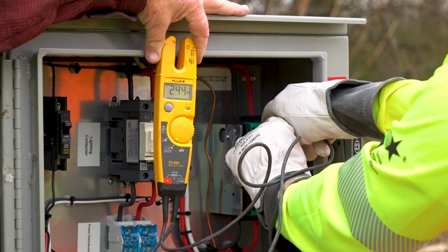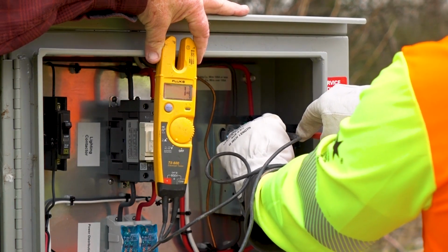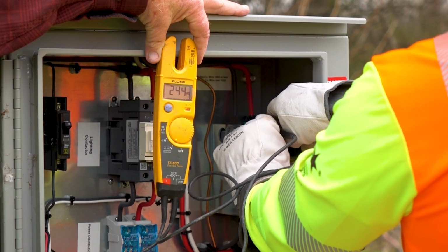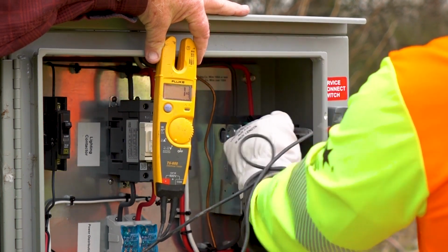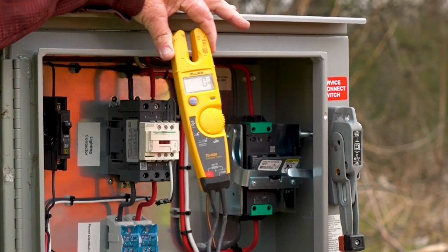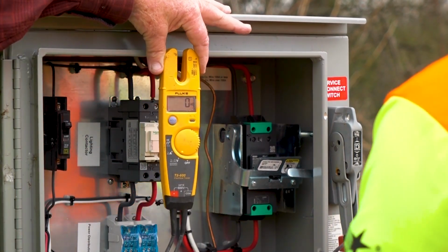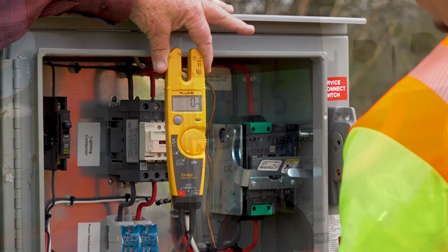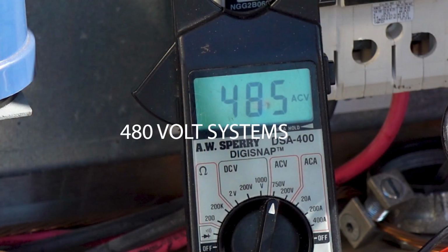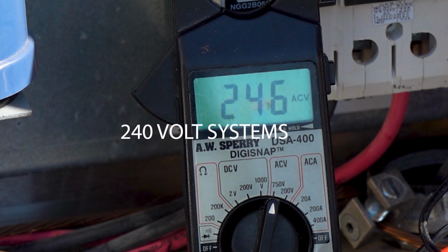After the utility company has installed the meter and connected power to the service entrance conductors, but before the main breaker is turned on, the following voltage readings must be taken and recorded in the presence of either the engineer or the electrical inspector. On 480-volt systems, the voltage between line 1 to line 2 should be within 5% of the nominal voltage, or between 456 and 504 volts. On 240-volt systems, the voltage should be between 228 volts and 252 volts.